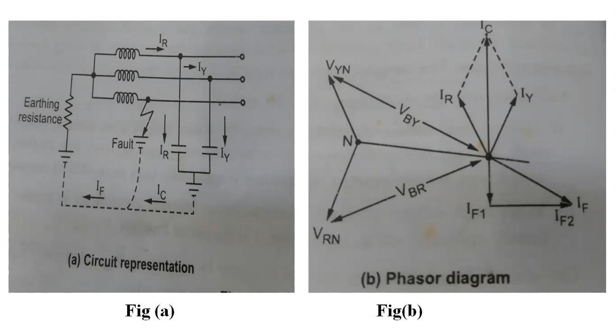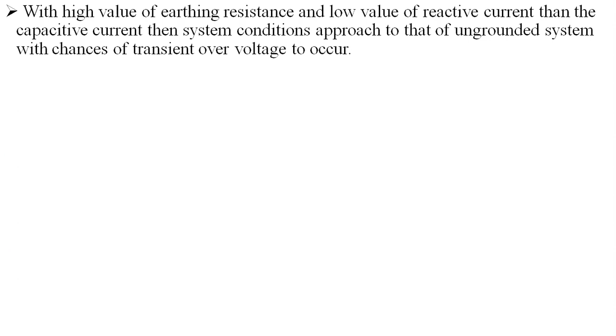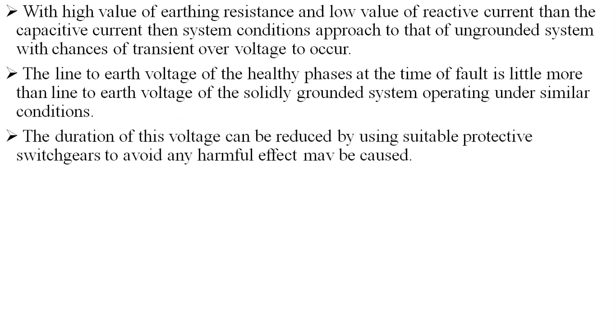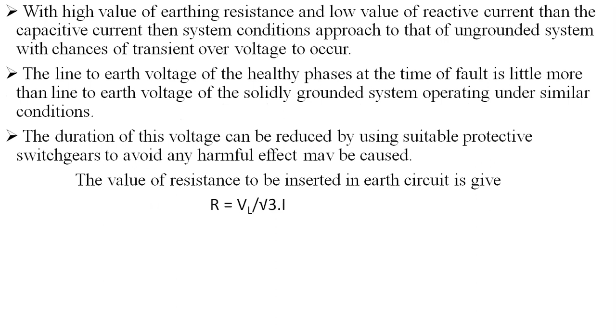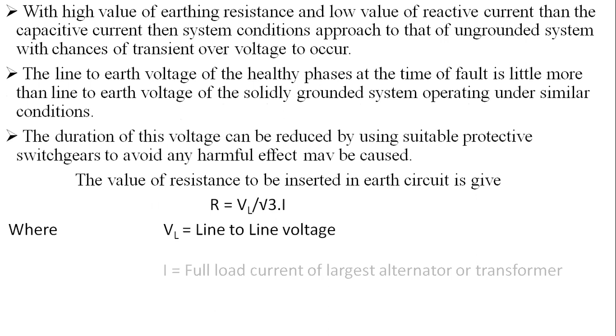With a high value of earthing resistance and a low value of reactive current compared to capacitive current, the system conditions approach those of an ungrounded system, with chances of transient overvoltage occurring. The line to earth voltage of the healthy phases at the time of fault is a little more than the line to earth voltage of the solidly grounded system operating under similar conditions. The duration of this voltage can be reduced by using suitable protective switchgear to avoid any harmful effect. The value of the resistance to be inserted in the earth circuit is given as R equals VL by root 3 into I, where VL is the line-to-line voltage and I is the full load current of the largest alternator or transformer.